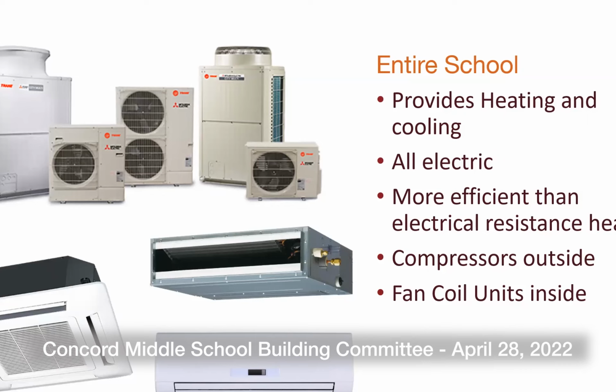Starting to talk about the internal layouts, we're going to use a mix of cassettes, ducted units, and wall mount units. In the classrooms, we're starting to look at using cassette units. The thought is that with cassette units, you can get sound levels down to about 30 dB, which is great for classroom settings. Additionally, with reduced ductwork, it allows for higher ceilings, so anything we can do to help architecture keep ceilings as high as possible is something we're looking at. With this, we'll decouple the ventilation from the heating and cooling—bringing ventilation into the back of the classroom, and putting heating and cooling in the middle of the space, toward the exterior.